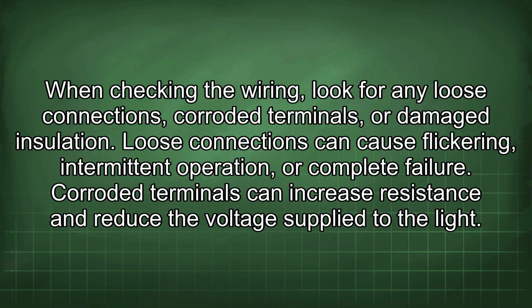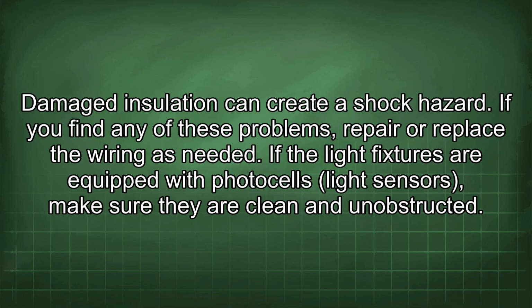When checking the wiring, look for any loose connections, corroded terminals, or damaged insulation. Loose connections can cause flickering, intermittent operation, or complete failure. Corroded terminals can increase resistance and reduce the voltage supplied to the light. Damaged insulation can create a shock hazard. If you find any of these problems, repair or replace the wiring as needed.